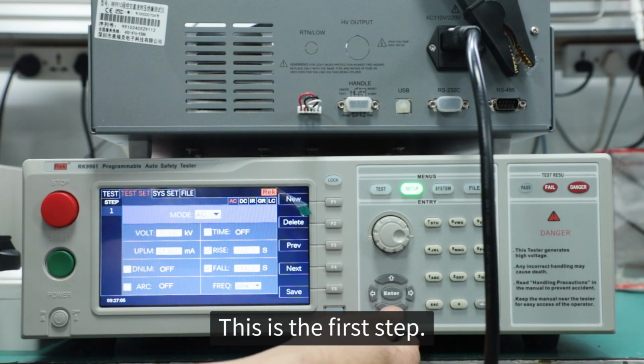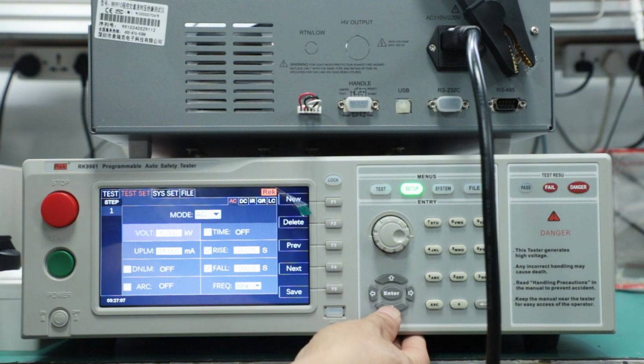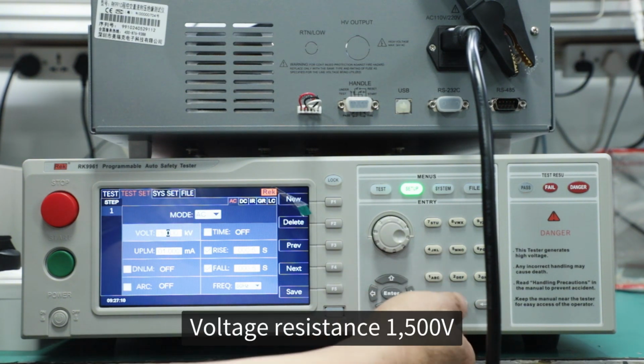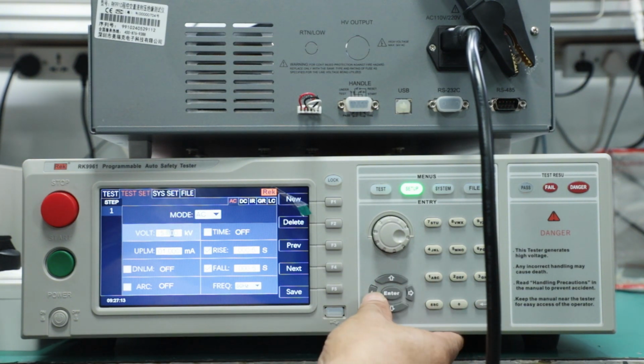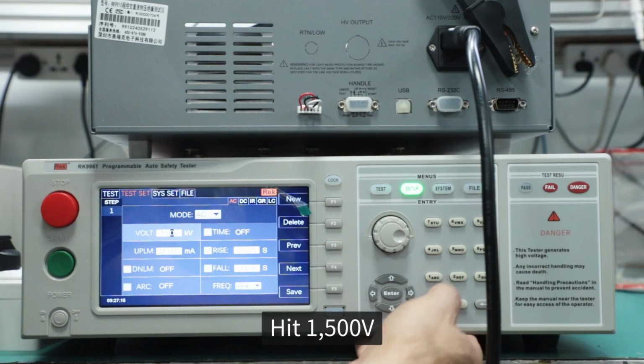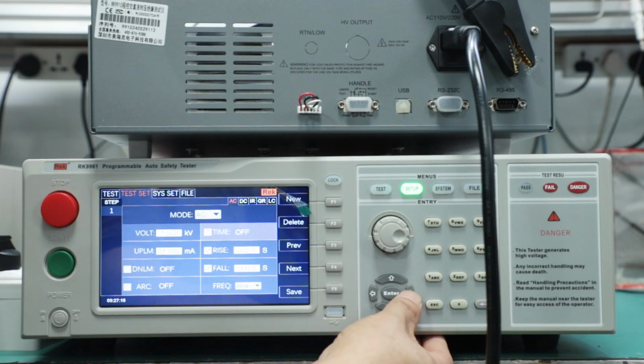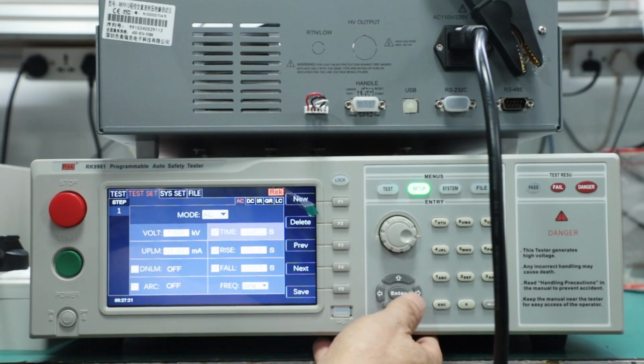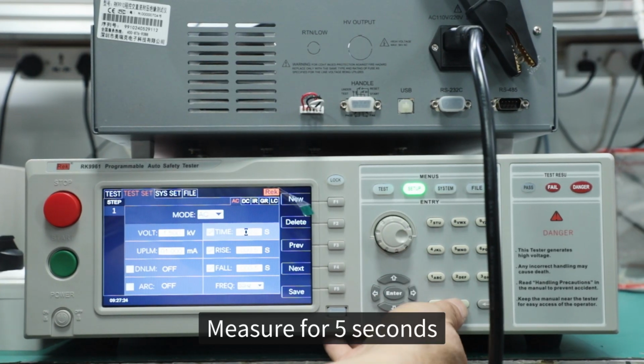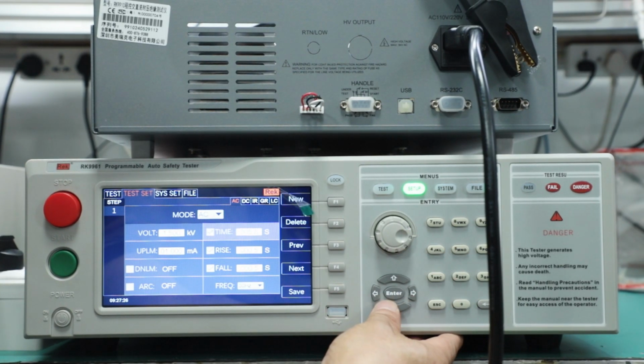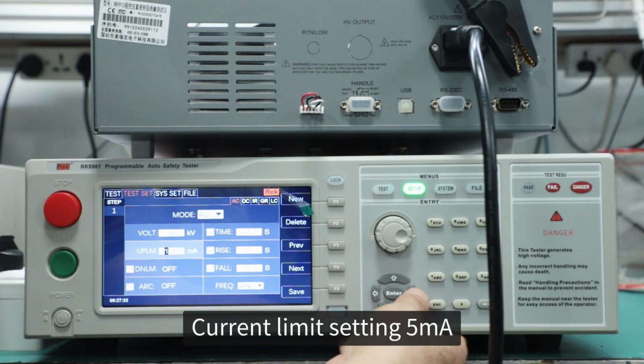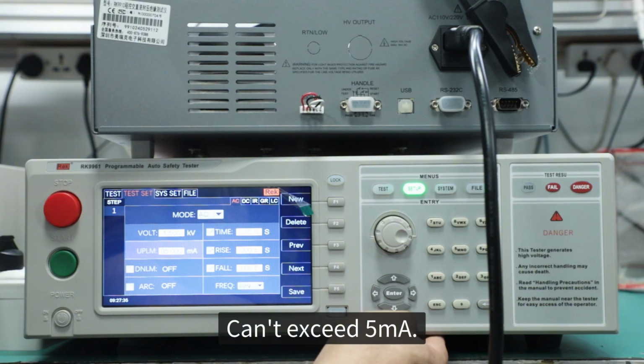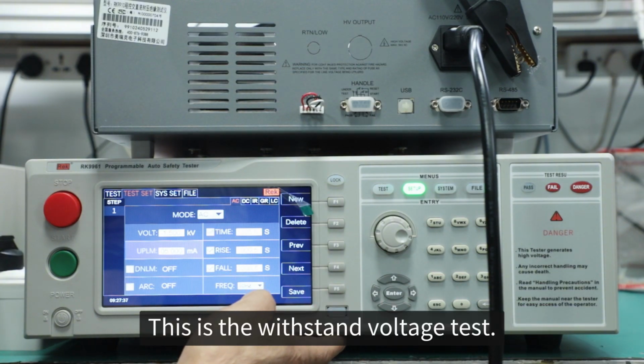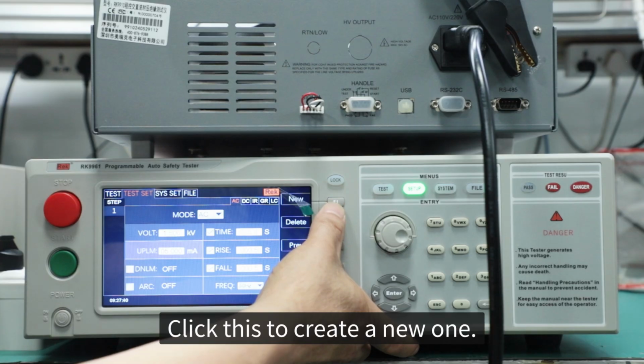This is the first step: measure AC withstand voltage. Withstand voltage 1500 volts. Test time, measure for 5 seconds. Current limit setting 5 milliamperes; it can't exceed 5 milliamperes. This is the withstand voltage test. It's set. Click this to create a new one.